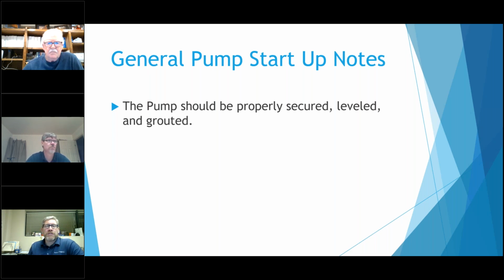The first thing: the pump should be properly secured, leveled, and grouted. I've seen a lot of base mounted pumps or motor mounted pumps that should be mounted to the pad, but they're missing some of the bolts, or they're not bolted at all. What can end up happening is the pump vibrates because it's moving, so you can actually see the pump bouncing on the pad. On some of the larger ones I've seen, they just put one bolt in. Well, the pump is so big and heavy that it's not going to go anywhere. But what they've actually created was a tuning fork effect, where one end of the pump is bouncing up and down, causing more noise, wearing out couplers and stuff like that.